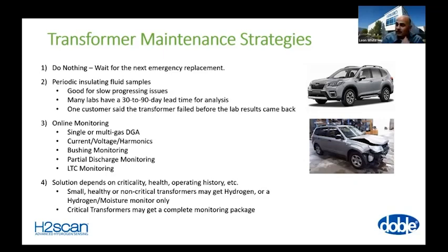On the fourth point, the solutions depend on criticality, health, operating history, et cetera. Typically, small, healthier, non-critical transformers may get something like a hydrogen monitor, or a hydrogen and moisture monitor only. Usually when people start doing monitoring, the DGA monitor is the first thing they'll put on, because looking at the insulating fluid and when gases are generated in that fluid is a good indicator - just like a blood test on yourself is good to get an understanding of how healthy you are.